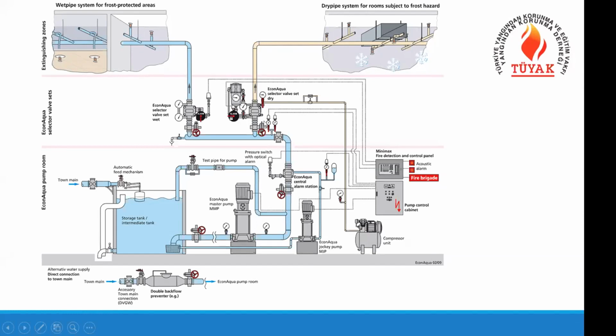So you have here, before the room, all the pipe empty and filled with pressurized air from a compressor. So this is a dry system. With the dry system, we are avoiding frost inside the pipe, and the system operation is possible: when the sprinkler operates, the air releases from the pipe and the water fills the piping and controls the fire.